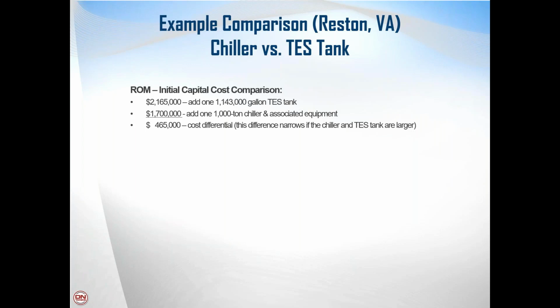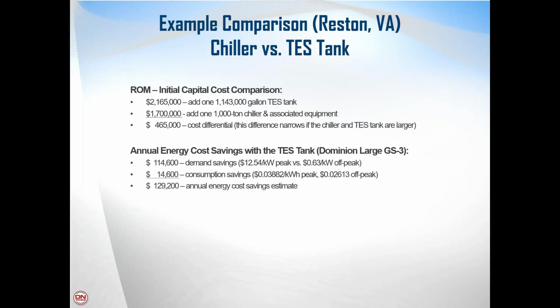So as I'm comparing now the chiller to the thermal energy storage tank project, you can see that the tank is going to be about $460,000 more than the chiller and associated equipment. But with the thermal energy storage tank and based on Virginia's electric rates, the owner is going to probably save about $130,000 a year on energy costs alone.